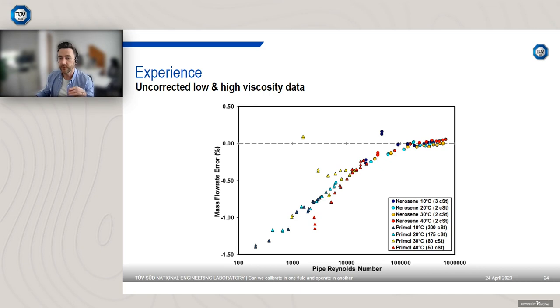The issue with this is, though, you would need to ascertain what the Reynolds number is of your fluid at flowing conditions. So you need to use the uncorrected mass flow, the pipe geometry. You need to then use the density from the device, and also have a handle on what the viscosity is. Now that fourth parameter there, the viscosity, is a challenging one. People don't always measure the viscosity of their fluid. So that means having a live dynamic correction is more challenging.